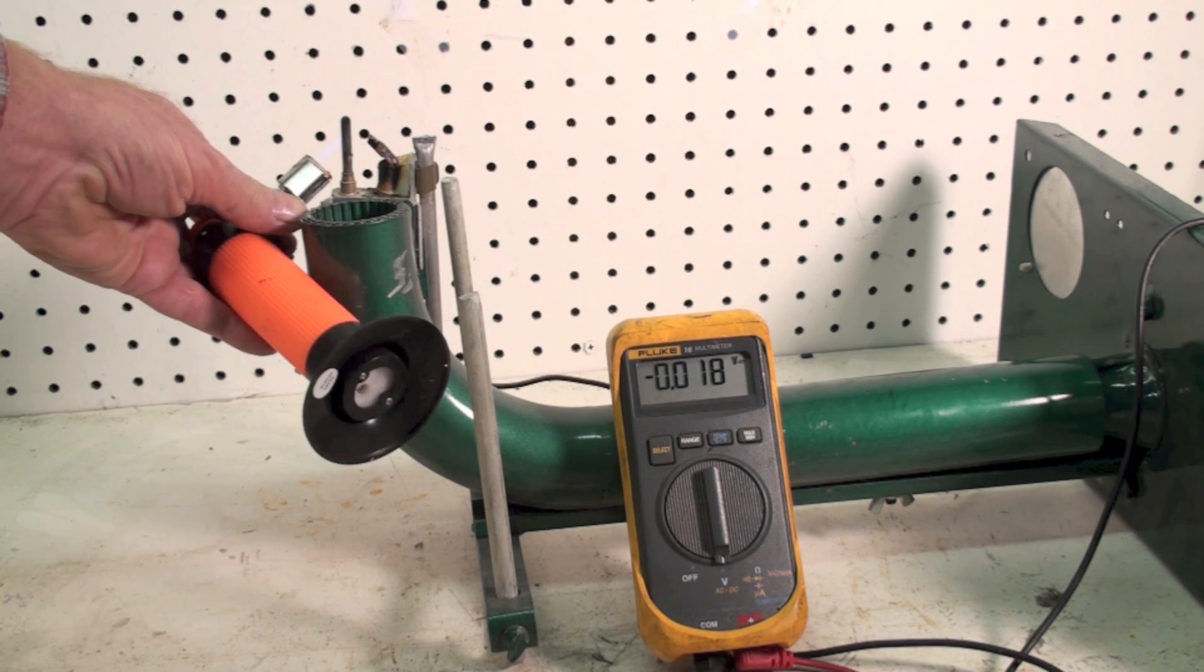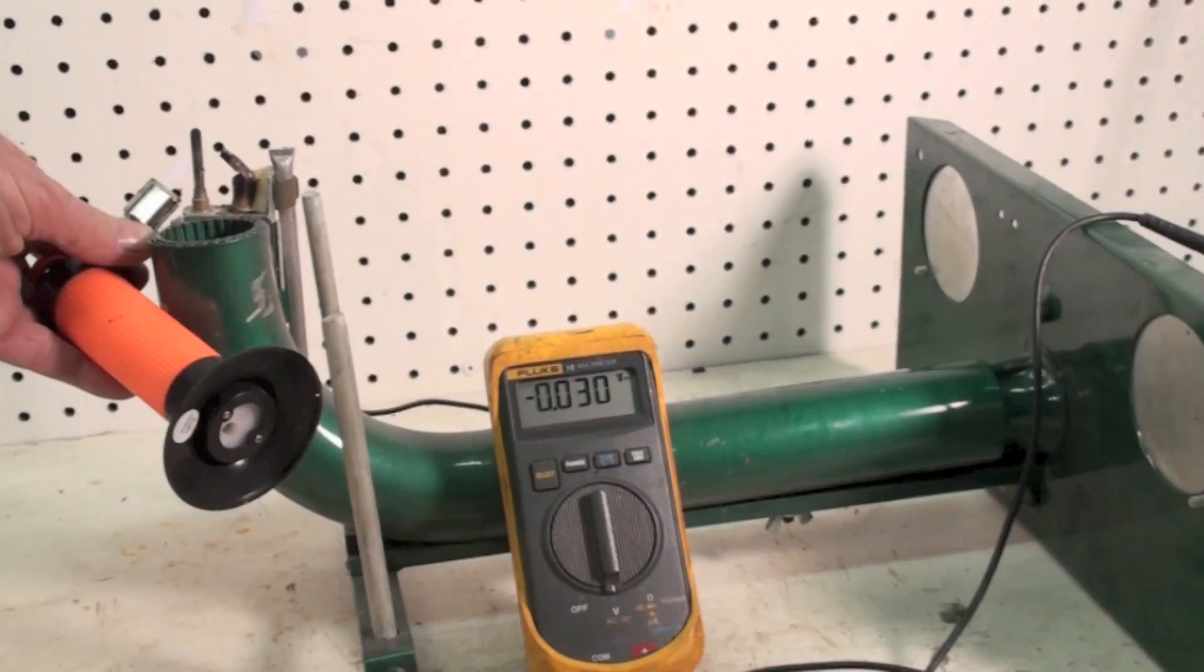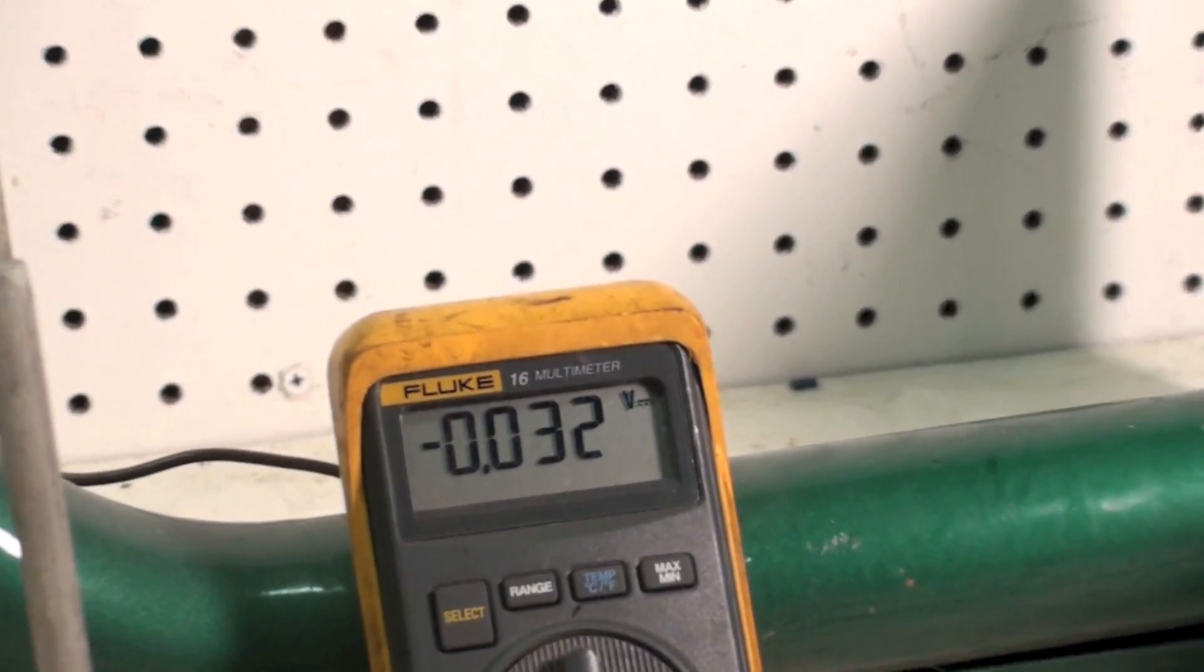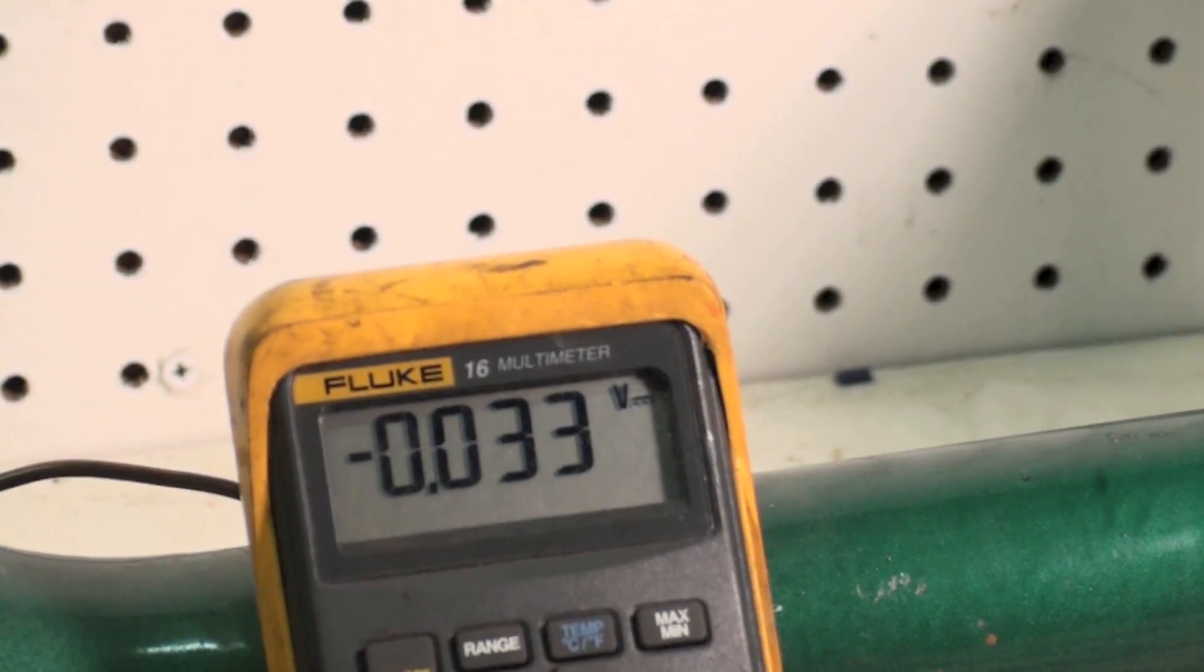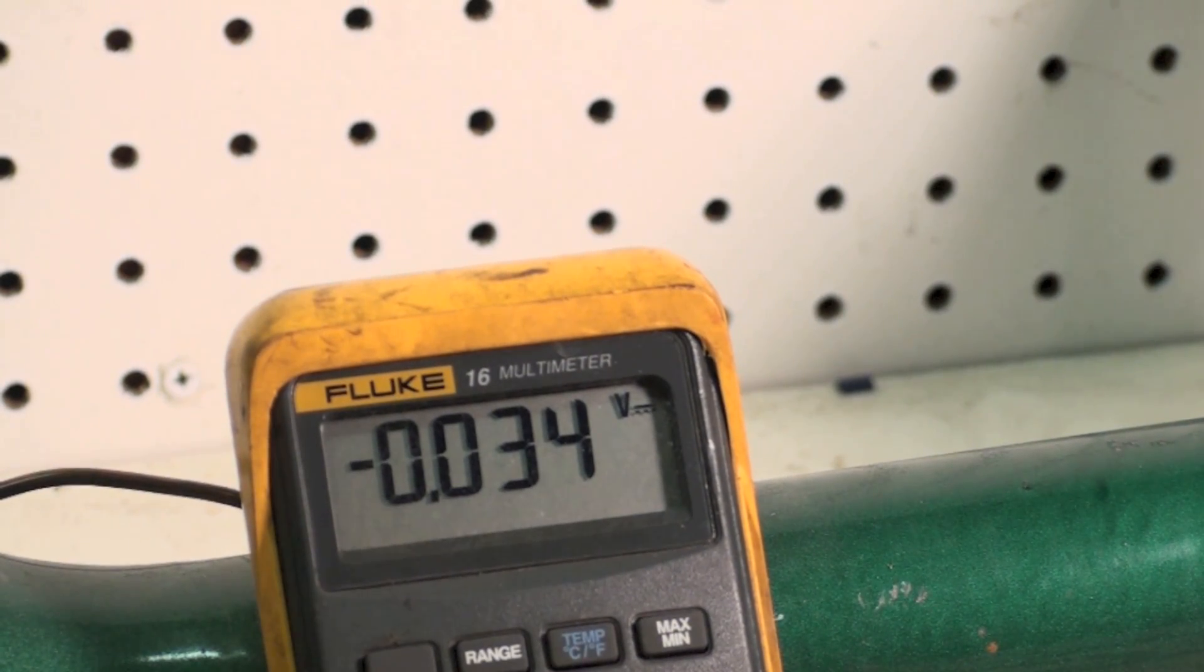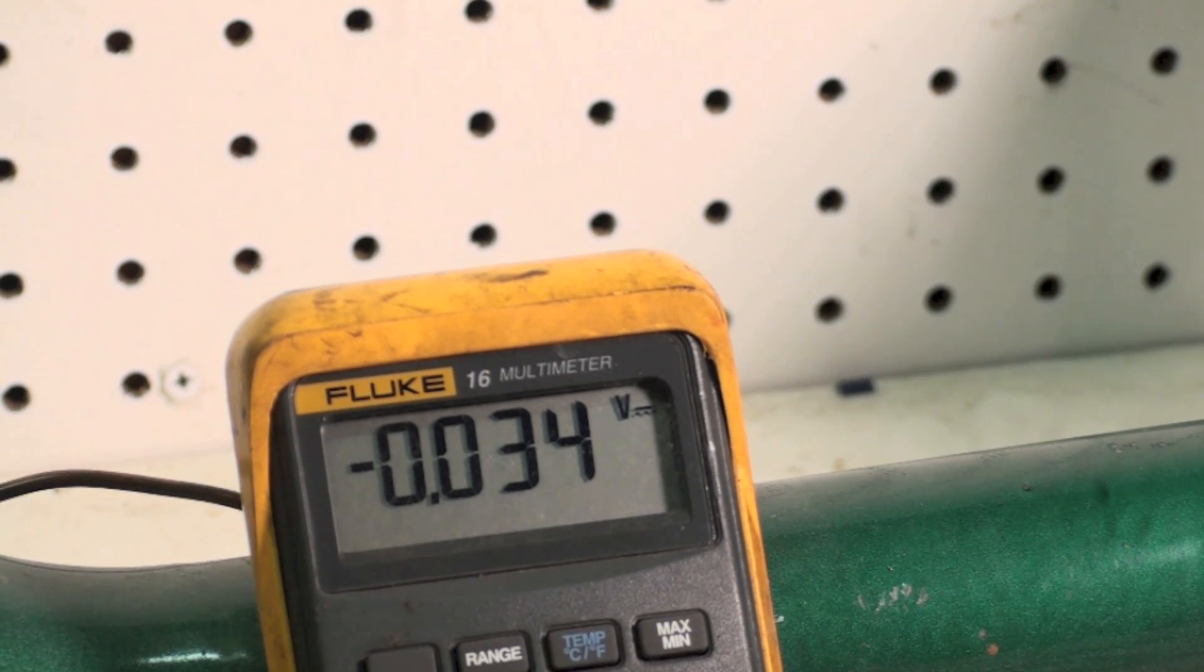You can see I'm going to max out around 34 millivolts. That's probably more intense than it'll ever be with the pilot on it, so the maximum is usually considered about 30 millivolts.